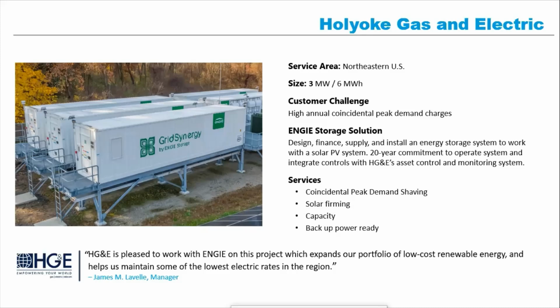So this is where we're able to operate both in front of the meter and behind the meter. This phase has now been running for over a year. They did not elect to do backup power, so we made it all backup-power ready, but our plan later this year is to run part of the local town on this grid. What we're missing is the connection and downstream relays from this facility to the town, and the ability to decouple the town so none of the linemen get injured. Once that's in place, we'll be able to run the town on this solution. It's an interesting way to manage that.